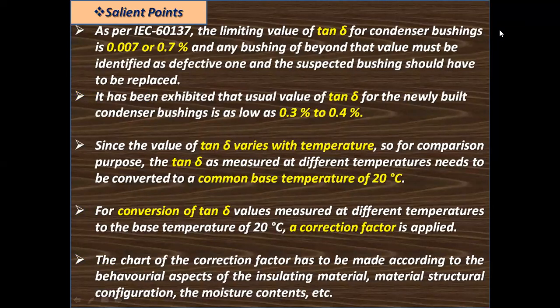Salient points to be noted. As per IEC 60137, the limiting value of tan delta for condenser bushings is 0.007 or 0.7%, and any bushing beyond that value must be identified as a defective one, and the suspected bushing has to be replaced. It has been exhibited that the usual value of tan delta for newly built condenser bushings is as low as 0.3% to 0.4%.